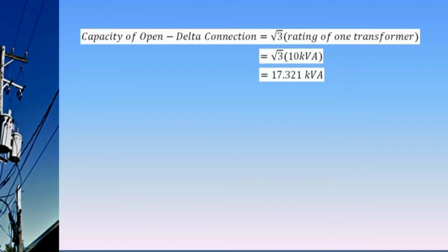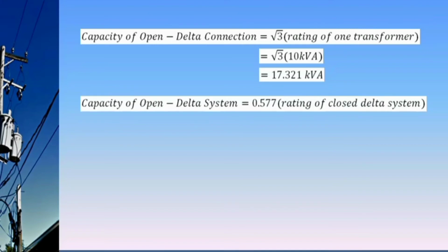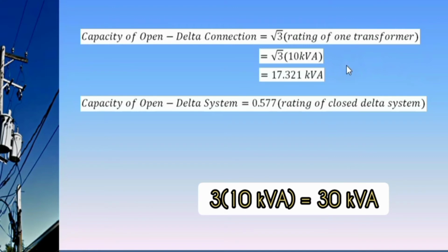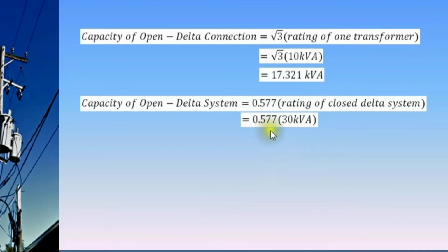Another way is by multiplying the rating of its equivalent closed delta system by 0.577. From our example, if each transformer is rated 10 kVA, its equivalent closed delta system will be 3 times 10, that is 30 kVA. So we multiply that by 0.577. 0.577 times 30 kVA, that is 17.31 kVA, which is near the value that we have computed above.